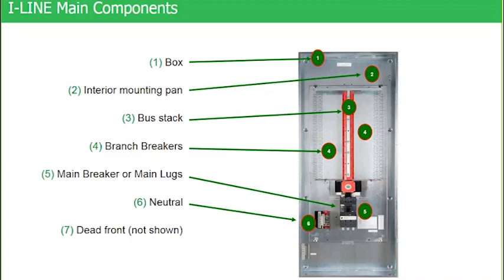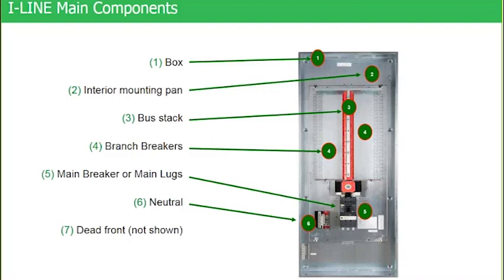I want you to focus on that bus stack and look directly above that vertically mounted main breaker and you see a square red shape and that's a glastic material. By glastic I mean a mixture of fiberglass and plastic. And then you see a bolt with a Belleville washer and a nut right in the middle of that red square. And that's what really holds the bus stack together with those t-bone connectors that I mentioned.